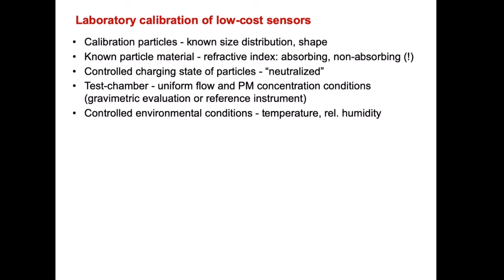We need calibration particles. We need to know the material of the particles. We can control the charging state of the particles - are they neutralized, with no electrical charge, or are they electrically charged? Why am I addressing this? Because if particles are electrically charged, the low-cost sensor casing, usually made of plastic, can have static charge islands on its surface. Electrostatic force is by far the largest force when it comes to removal of particles, so small charged particles will be removed within the sensor and not measured.